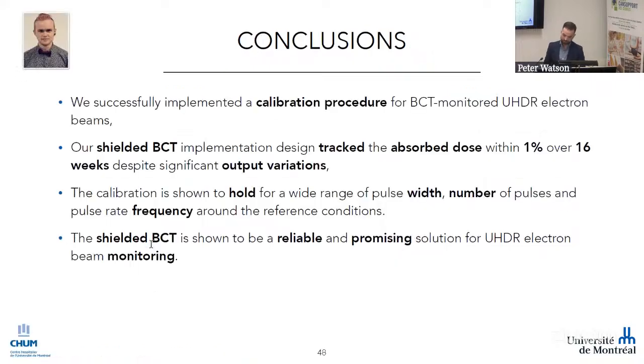So the conclusion of that work was that we were able to successfully implement a calibration procedure to monitor the dose with our BCT in the UHDR conditions. The shielded BCT implementation was able to track the absorbed dose within 1% over 4 months, despite significant output variation. To put that into perspective, previous studies that tried to do this with an unshielded BCT had stability more in the order of 2, 3, 4%. So it's a substantial reduction.